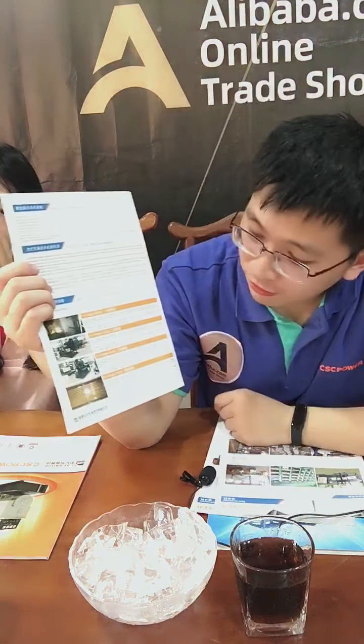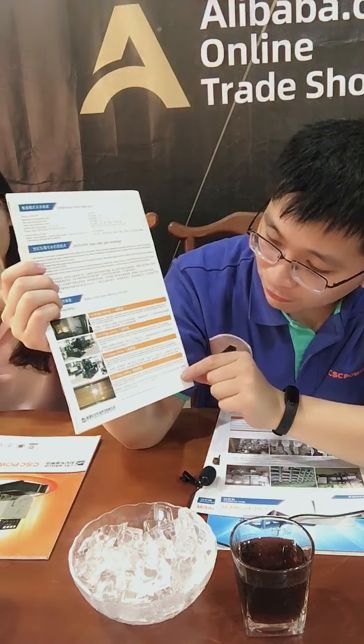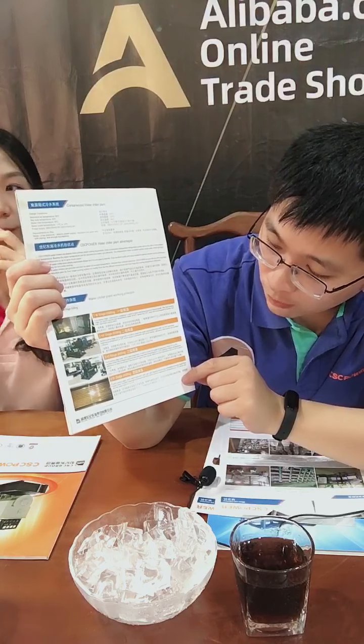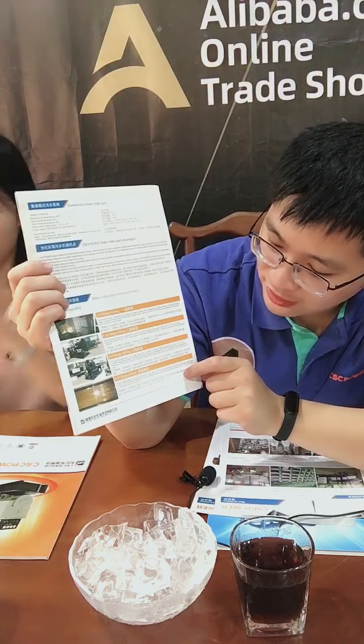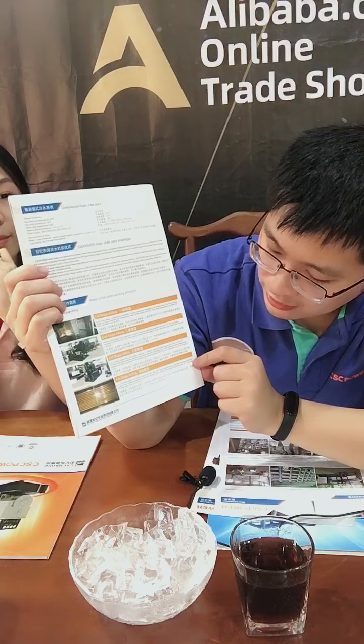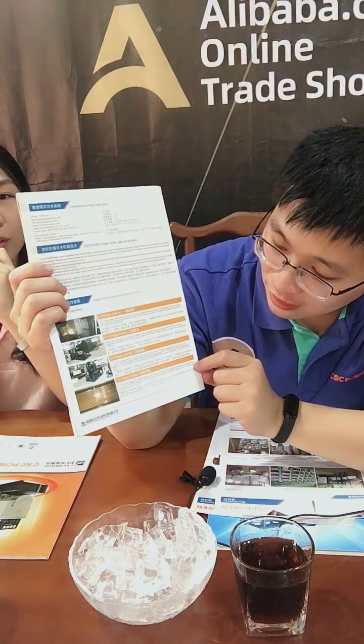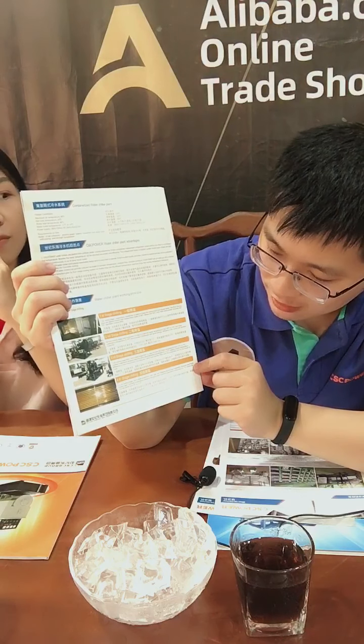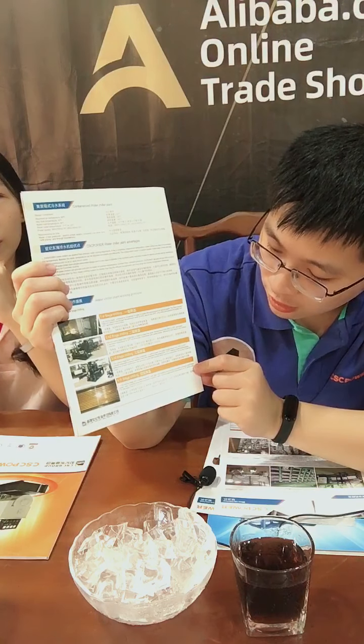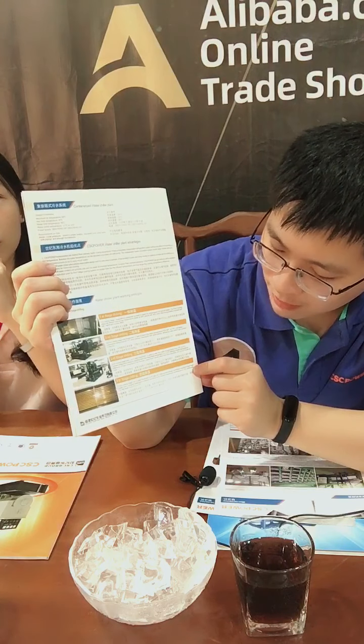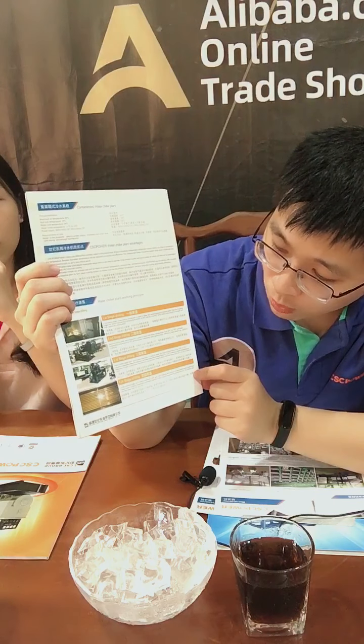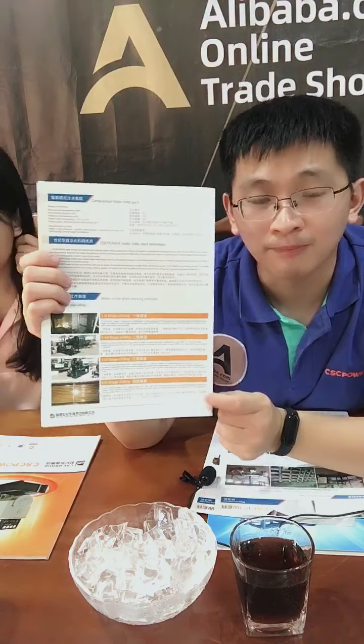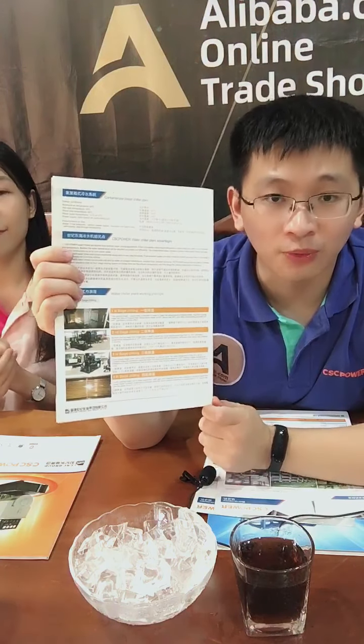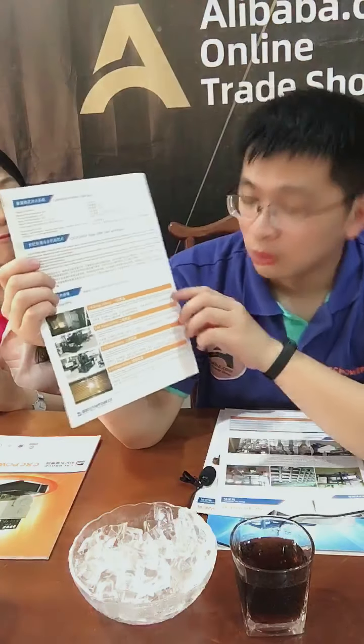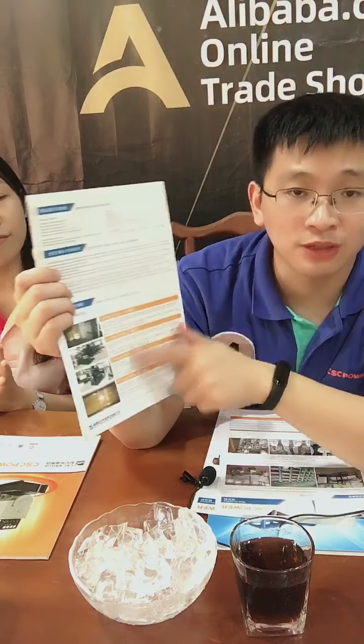We use evaporative pressure to adjust the temperature. It's our new technology. The fourth cooling stage is a coil or plate evaporator with gas anti-freezing technology, which completely prevents freezing and cracking. Constant evaporative pressure and adjustable controls keep the evaporative temperature at -5 degrees, which can chill the water from 4 degrees to 0.5 degree, very near to 0 degrees. This is our water chiller with more technology and four stages.